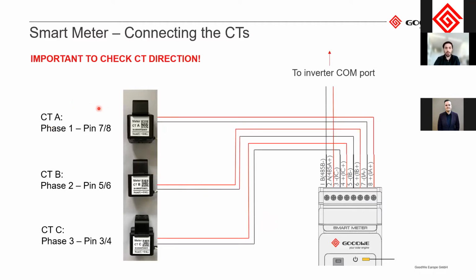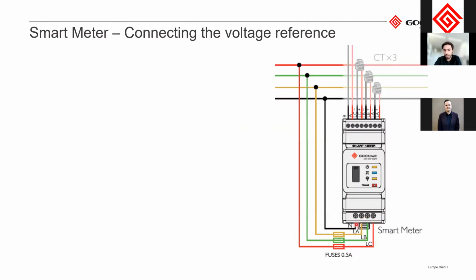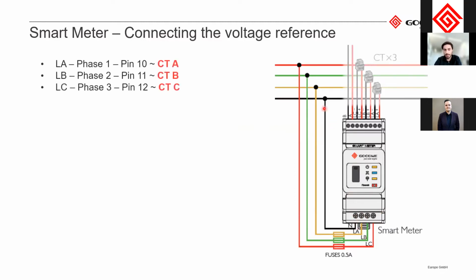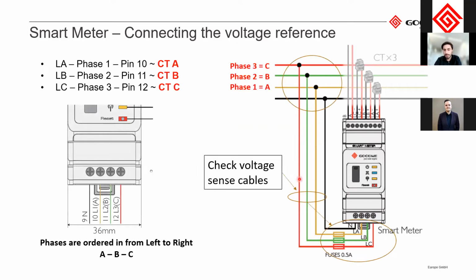As you see here, the CTs are also marked with CT A, B, and C. So for phase 1, 2, and 3. Here you can see that the first phase is connected on the right-hand side, and then the phases go from right to left here. But if you check the voltage sense here on the bottom side, they go from left to right. So here you see that the first phase is connected here to the left after the neutral cable. So make sure that you connect the corresponding voltage sense to the corresponding CTs. Otherwise, it will look funny in the monitoring portal.